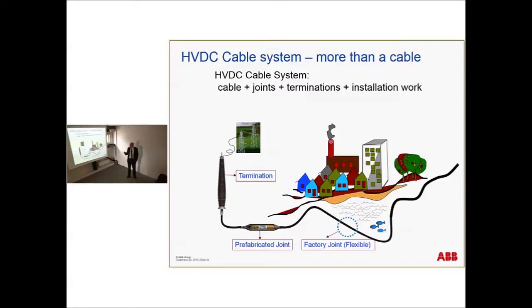The system here, well, we have the cable, of course. We need to have joints, either factory joints, which will not be visible at all, or sometimes, if you have a longer route and need to go two times with the boat, then you need to have a prefabricated joint or a subsea joint. And then we have the termination, where you go from high voltage. Here it's an insulator with a conductor inside, very similar to an instrument transformer. And if you want to go back over to an overhead line or a switchyard. So it's a complete system, and I would say the most tricky thing is the installation work.